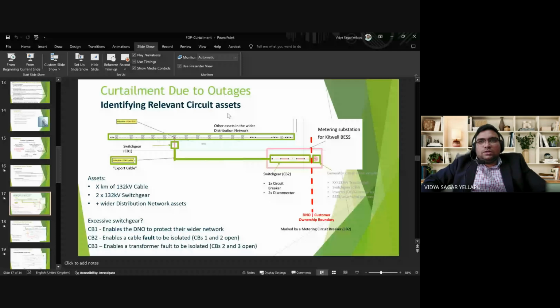This is the continued discussion on curtailment due to outages. Suppose a generator is getting connected here. It is a renewable energy source, and as it is renewable in nature, its power is to be converted to AC, so there is a need for an inverter and switchgear. The generation is normally around 690 volts, or 0.7 kilovolts. It is to be stepped up to 132 kV, because this wider network is at the 132 kV voltage level, so a transformer is needed. The generator constitutes the base, solar or wind, followed by the inverter, switchgear and the transformer. And this is the wider network.